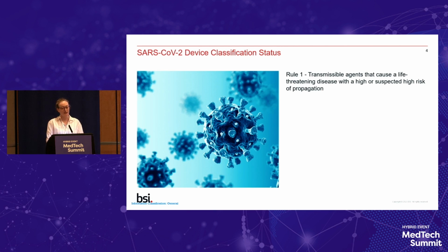So they're classified as Class D under Rule 1. They're also listed as an example in the MDCG 2020-16 Rev 2. So that's the classification guidance document. And as Marta said, at the moment, notified bodies are still regarding them as Class D, despite the guidance. It is only guidance, it's not legally binding.